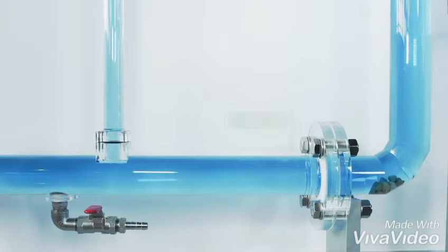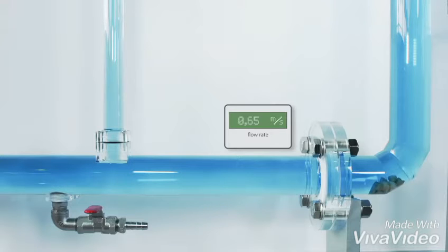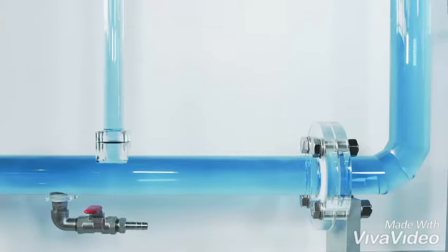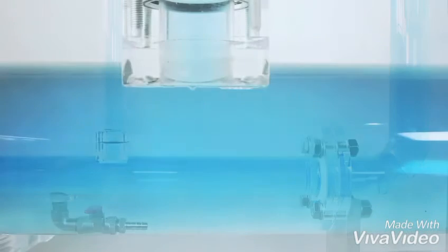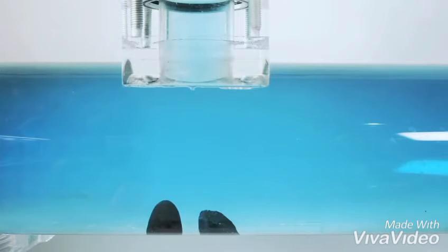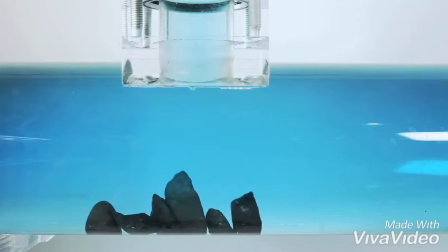For these solids to be transported out of the pump together with the fluid handled, a minimum flow velocity is required. Varying conditions must be taken into account, such as the different flow velocities for vertical and horizontal pipes, the inside diameter of the pipe, and the composition of the fluid handled.